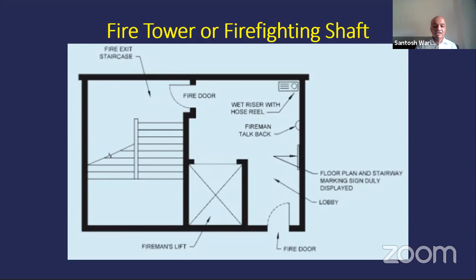So this is the fire tower wherein from the common passage you enter the fire tower through a fire door having 2 hours fire resistance. It has one fire lift, one fire escape staircase, a wet riser with hose reel and talkback facility, and the detailed layout plan of the floor. This helps the firefighters to reach the seat of fire for firefighting, and also for carrying out guided evacuation. This lift can be used for evacuation also. And this entire thing is pressurized with positive pressure so that no heat and smoke can enter the fire tower.